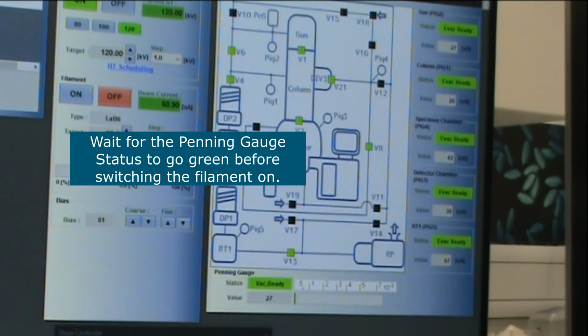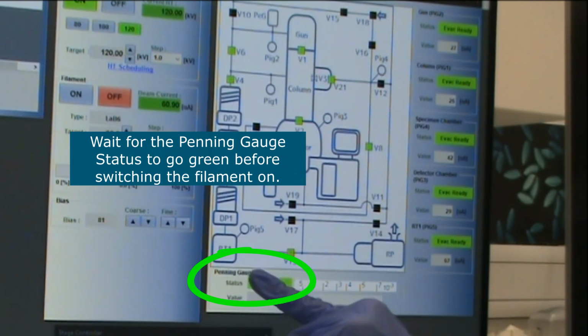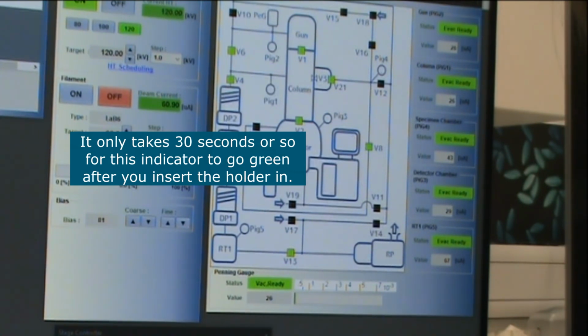After you have fully inserted the holder into the microscope, just wait for this vacuum indicator here to go green, ready. It's the penning gauge status. It only takes about 30 seconds for this to go green after you've inserted the sample holder into the microscope.